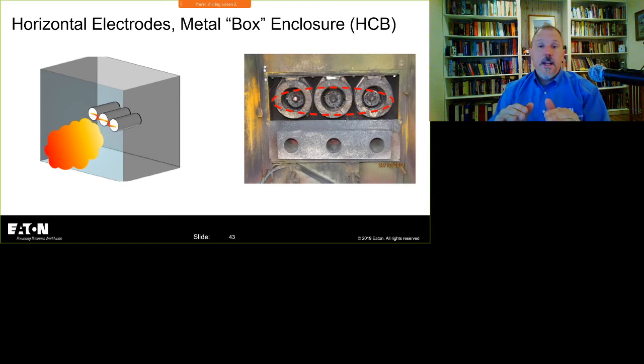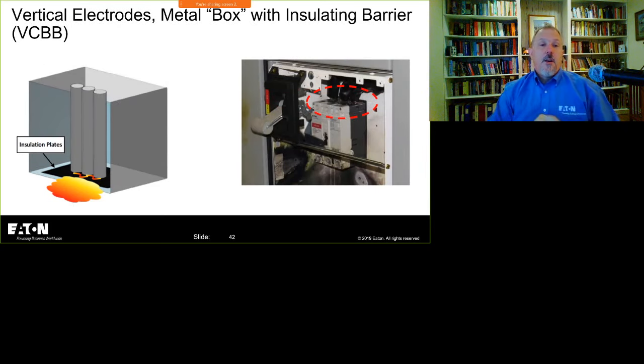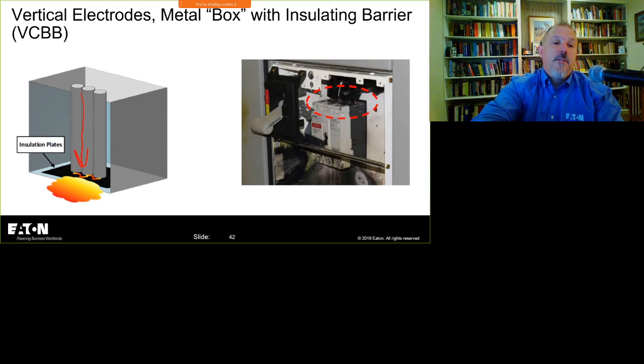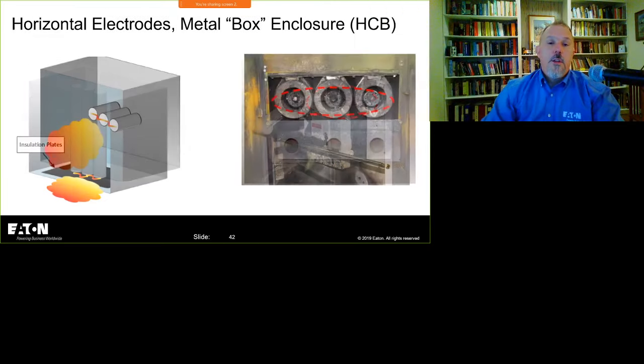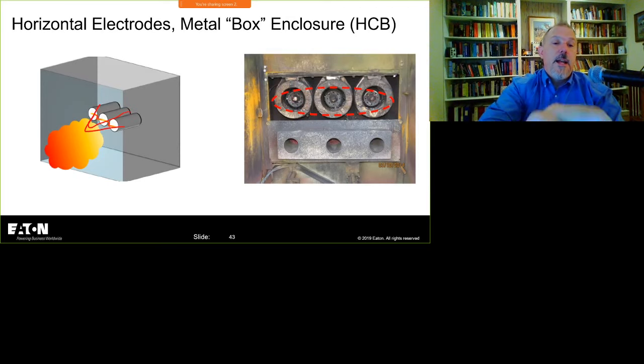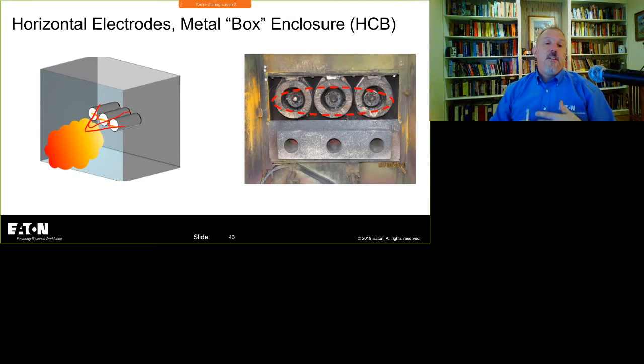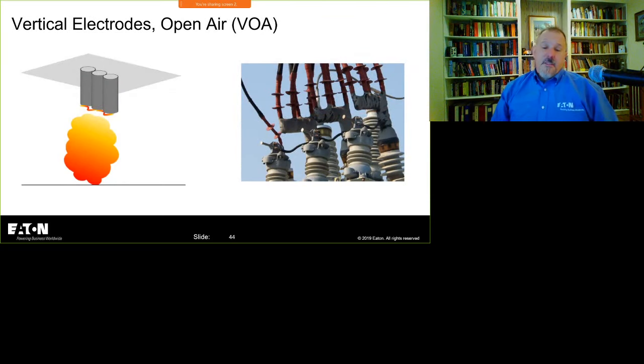This is when that bus is looking right at you. And I'm telling you, if you're an electrical worker, this is the worst case for you because that's the energy. Remember, the arc always flows away from the source down the bus. And if the end of that bus is pointed right at you, it's coming right at you. When you look at the vertical bus with barriers, the arc flows away from the source, which is down that bus, and then it flows into the barrier, and then that little plume pushes out. When you are looking at this, it's coming straight out at you. There's nothing barriering it off or anything like that. So this is your worst case from an incident energy perspective. And from an arcing current perspective.